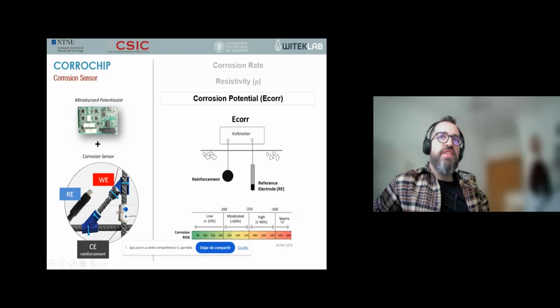Okay. The other parameter we obtain with Corrochip is the corrosion potential, as our reference electrode is included in the measuring cell. So this is a measurement of the electrical potential of the reinforcement, as its potential becomes more negative when the corrosion process is more active. This is actually a relative measurement, since the potential difference between the reinforcement and the reference electrode is recorded.